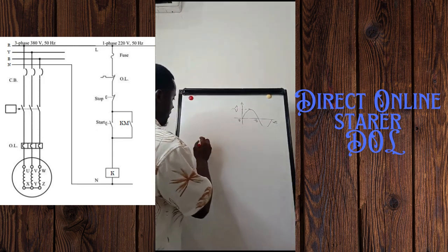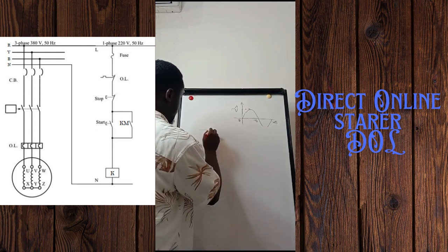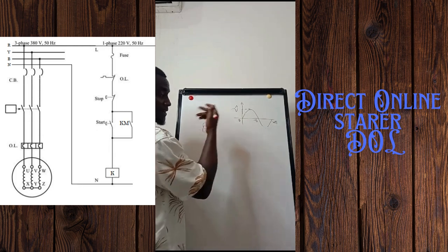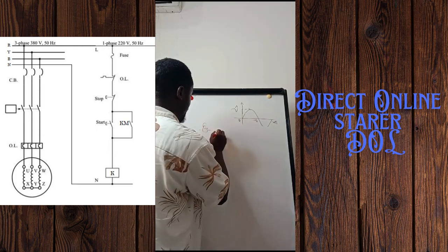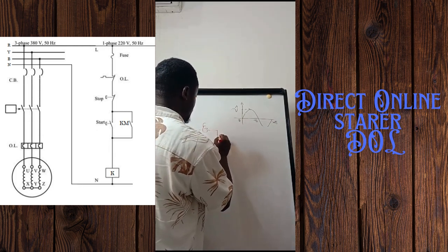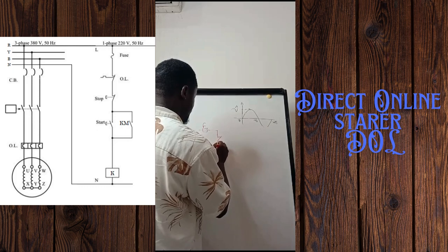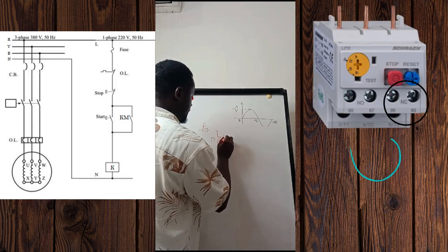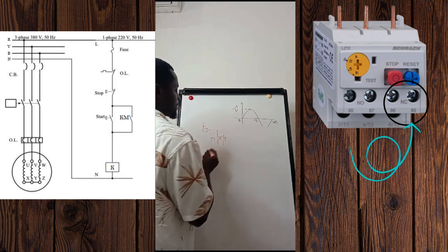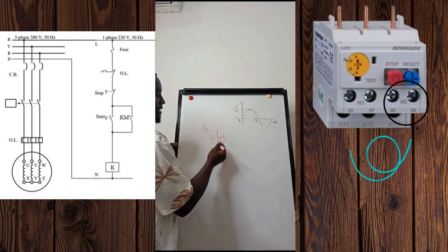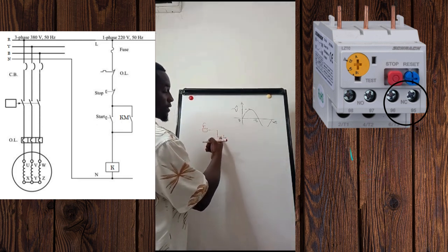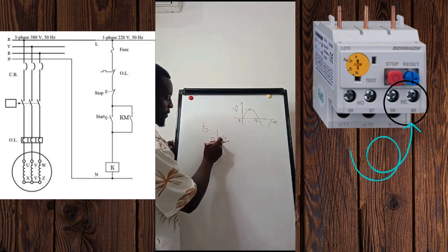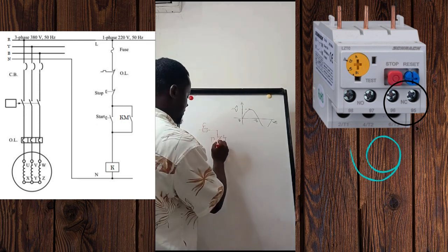To start with a direct online startup, we need a fuse or a circuit breaker. The next component we need is a thermal relay. We are going to connect it to a normally closed contact, and as we keep going, you'll understand the reason why we are connecting to the normally closed contact of the thermal relay.